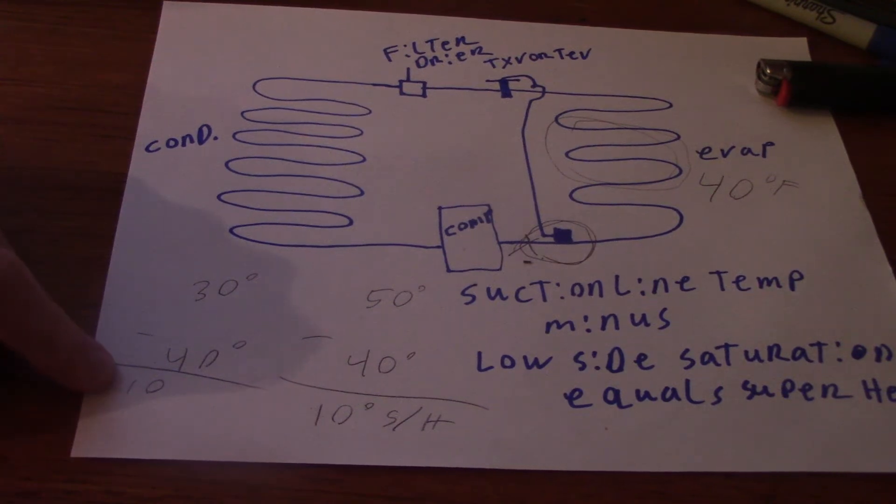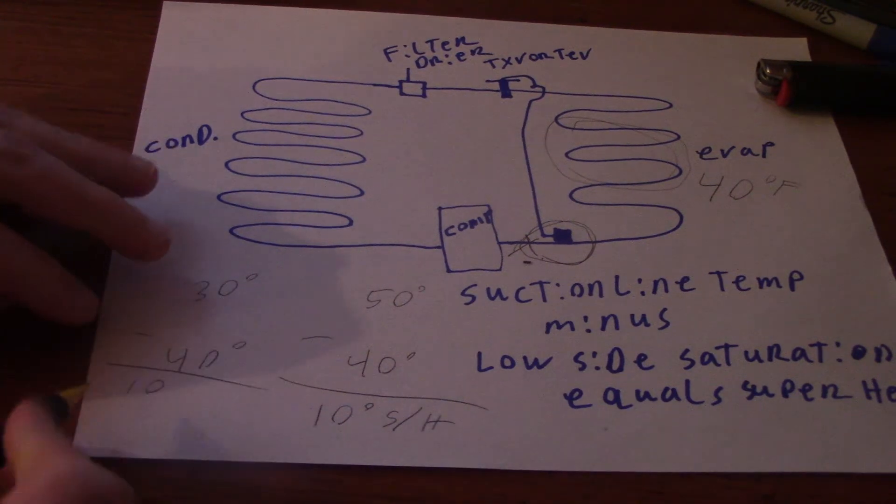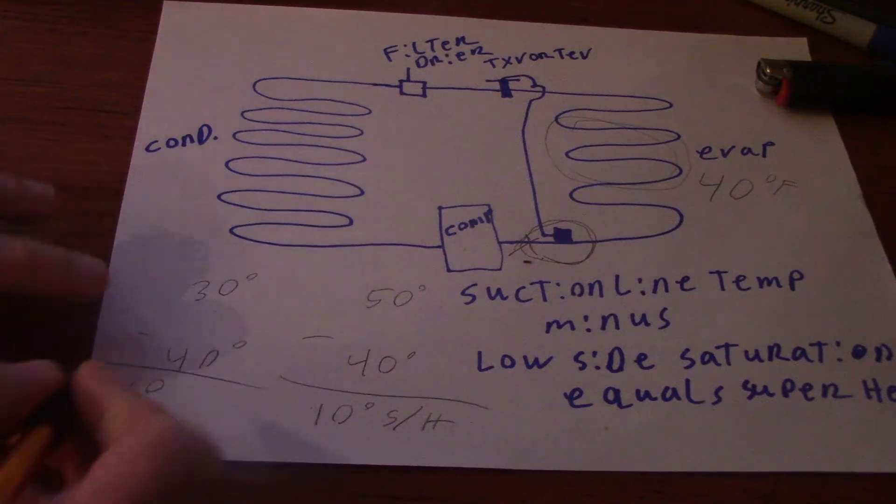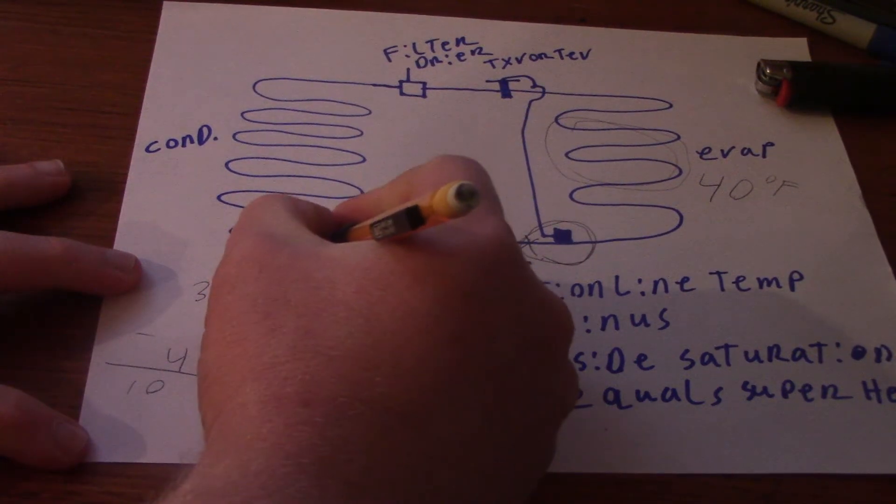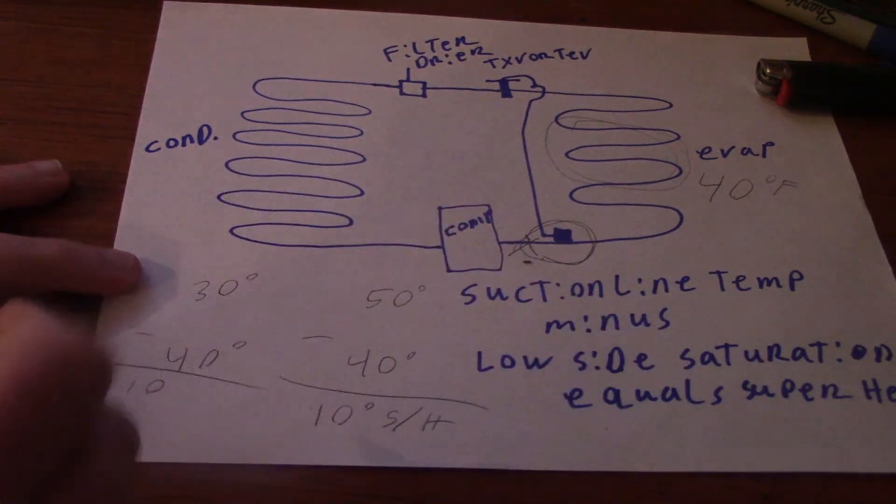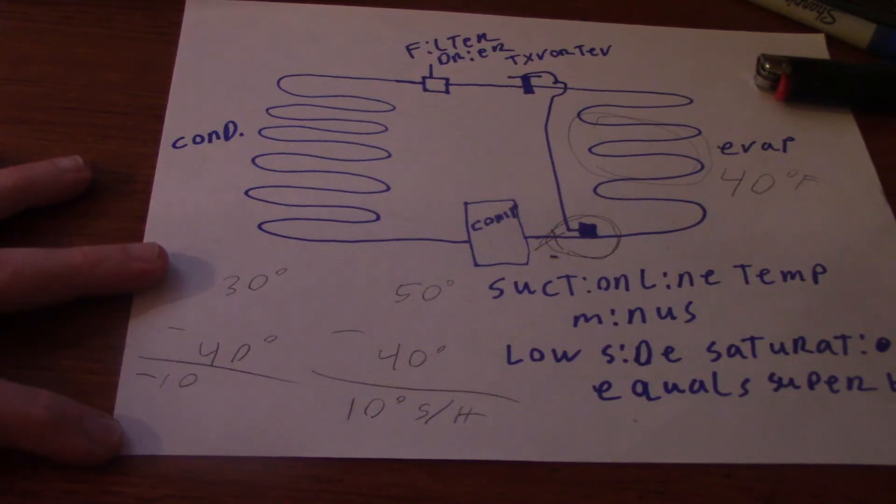hey, this system got to be working okay, because I got 10 degrees superheat. No, you're wrong. You did it backwards, so you got the wrong number. Reality is, you would have 40 minus 30, or 30 minus 40, which means negative 10.